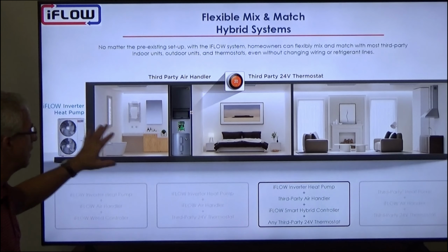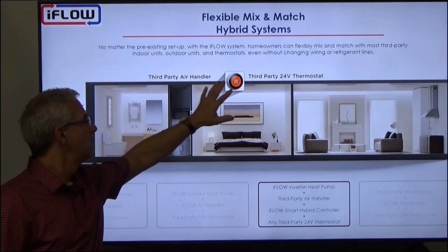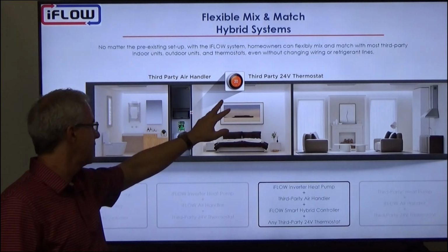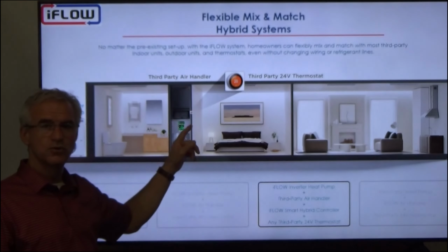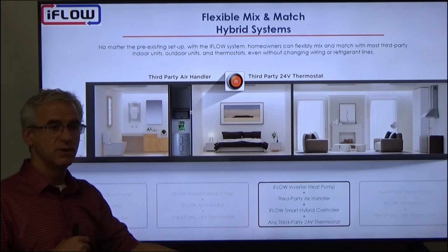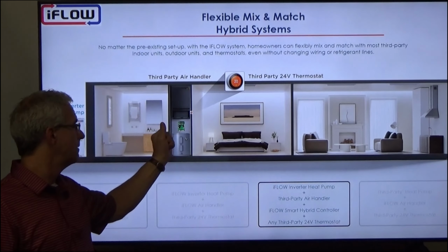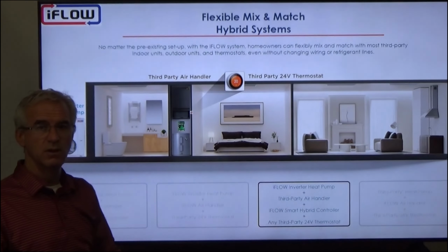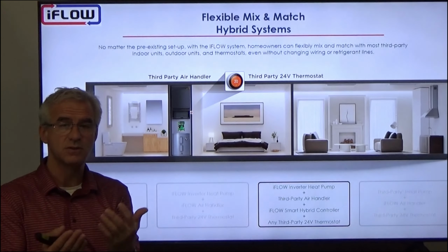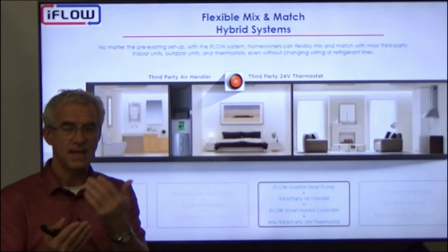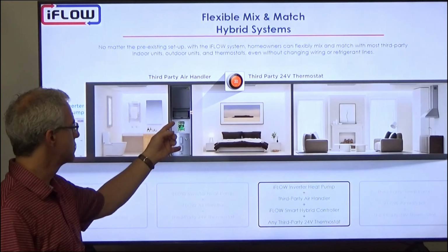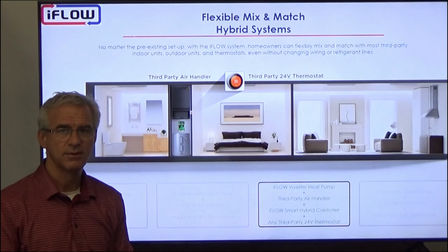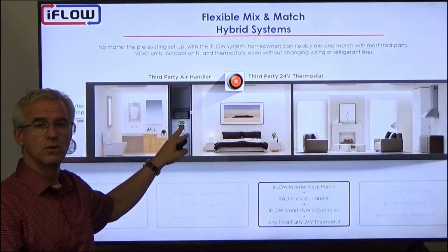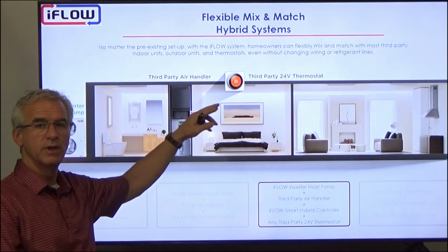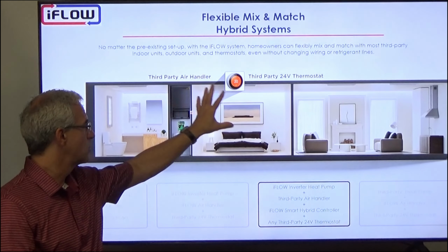So next option, now we're running with the outdoor unit, right? The same iFLOW outdoor unit. We're running with a third-party air handler or a furnace, for example. We're running with a third-party 24-volt thermostat. All we're doing though is adding the iFLOW hybrid smart controller. So when we add a heat pump to an existing system, let's say you had a furnace and an old AC unit, we switch out the AC unit and add the heat pump in. Now we're creating for the first time the ability to do heating through your heat pump and or through your gas side. So we have a little switching controller made by iFLOW that can take the signal from the thermostat. So the heating call from the thermostat comes into our controller, and then again we decide whether we bring the heat pump on or whether we bring the hydronics-based or the gas-based system on. So that's what we're showing in this option.